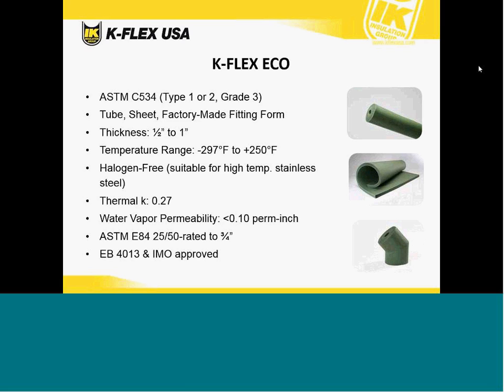K-Flex Eco product, ASTM C534 Type 2 Grade 3. It's tubes, sheets, and factory-made fittings. It's available in ½ inch up to 1 inch. Temperature range is from -297 Fahrenheit to +250.